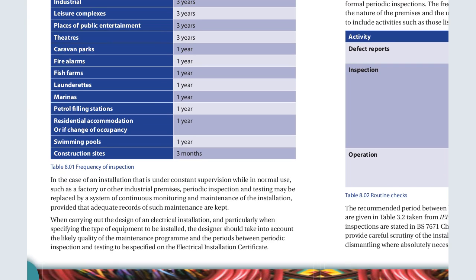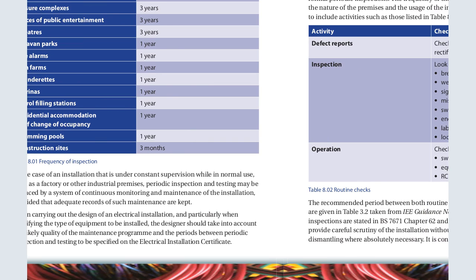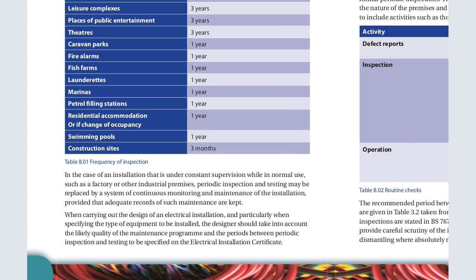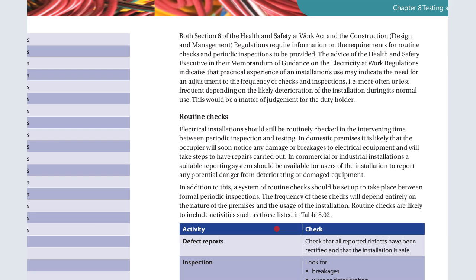In the case of an installation that is under constant supervision while in normal use, such as a factory or other industrial premises, periodic inspection and testing may be replaced with a system of continuous monitoring and maintenance of the installation, provided adequate records such as maintenance records are kept. When carrying out the design of an electrical installation, and particularly when specifying the type of equipment to be installed, the designer should take into account the likely quality of the maintenance program and the periods between periodic inspection and the testing certificate.